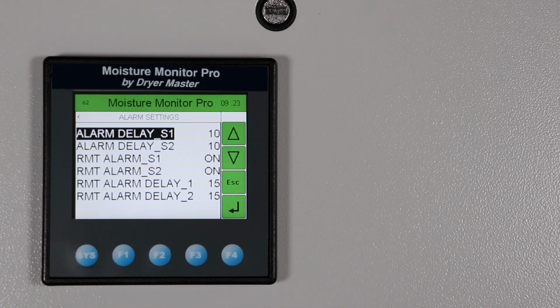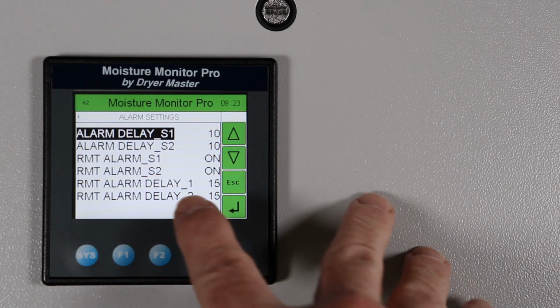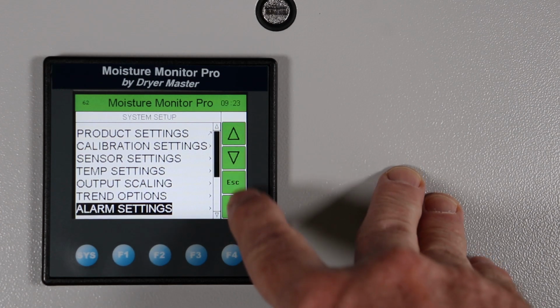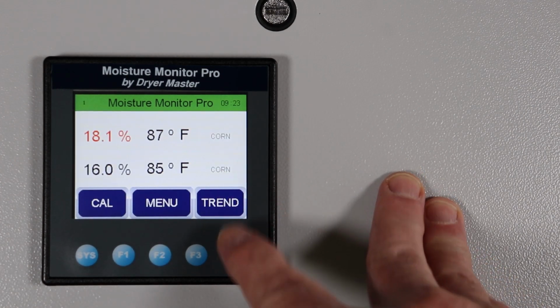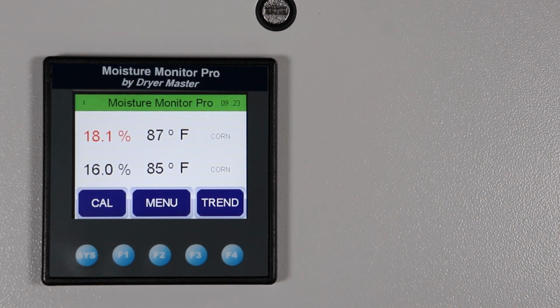The 10 is 10 seconds, so it has to be an alarm for 10 seconds before the alarm goes off. And there's also a remote alarm, so if you want to set up an alarm, say out at another part of the site where you're going to wire it up and there's going to be a sound going off if it's an alarm, you can do that as well. And the remote alarm is already set up to be on if it's plugged in. And then you can also set a remote alarm delay there as well. That's the one down here. Okay, so that's essentially what we have to do with alarms.